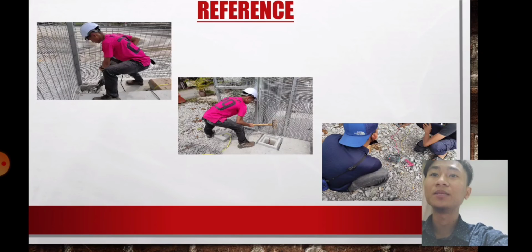After pasting the cement around the copper tape route, connect the copper tape and copper rod by using a clip rod and tighten the connection with nuts, and it is ready for the earthing testing using an earthing tester. Make sure the reading value is 3 ohm or below for good industrial earthing equipment, and submit the result to TNB. Okay, and then the last step is to pick up all the equipment and tools after finishing all the work in the workplace before leaving the workplace.